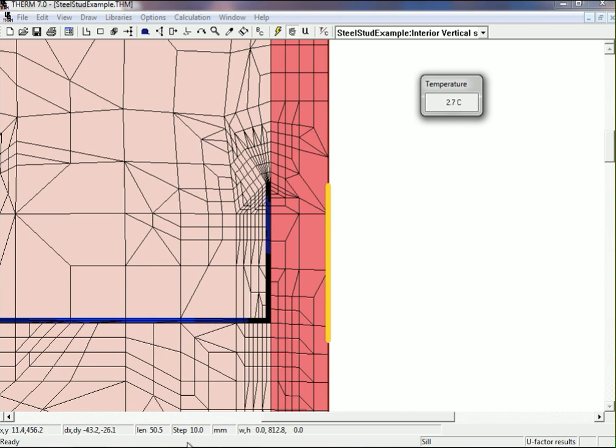So we had the dew point temperature, we're looking for 13.05. As we move along this surface, here it's 13.5, and then here the temperature dropped to 10.8. So the program is drawing in the midpoint here, even though it's 13.5 to 10.8. Somewhere in here the temperature drops below the dew point, and then along here it's 10.8, 10.2, 11.7, and then here the temperature is getting above that 13.05. So the program is highlighting the area of the cross-section that is under this 13.05 degrees Celsius, and that can be under condensation.